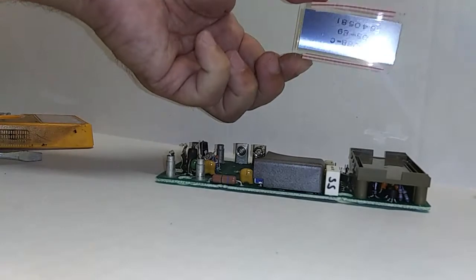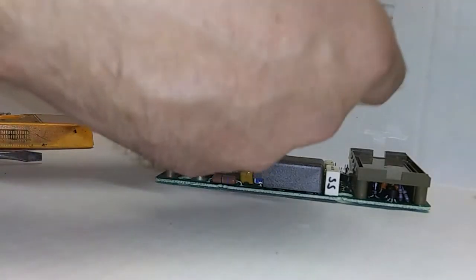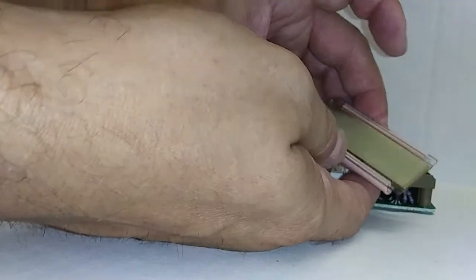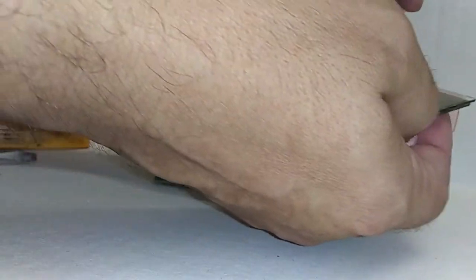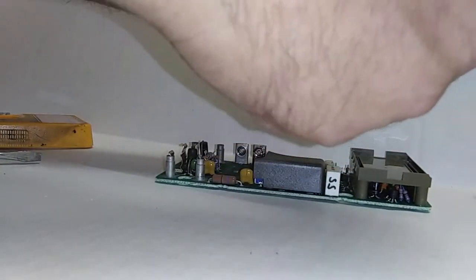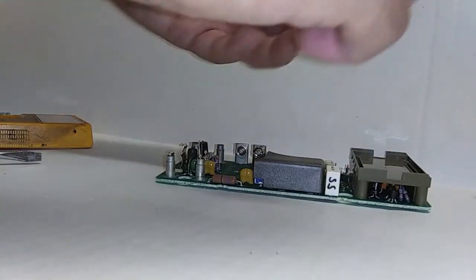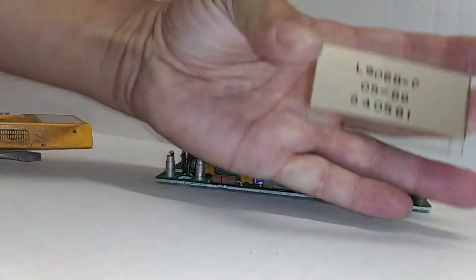It's normal, you're going to have these older units, these older elastomers kind of stuck in place on these LCDs. I want to catch my bearings, make sure I don't put it back in upside down. Anyway let's tear these off, these are the old ones. Won't be needing these, and this is the part number LCD, this is the Fluke manufacturing part number.